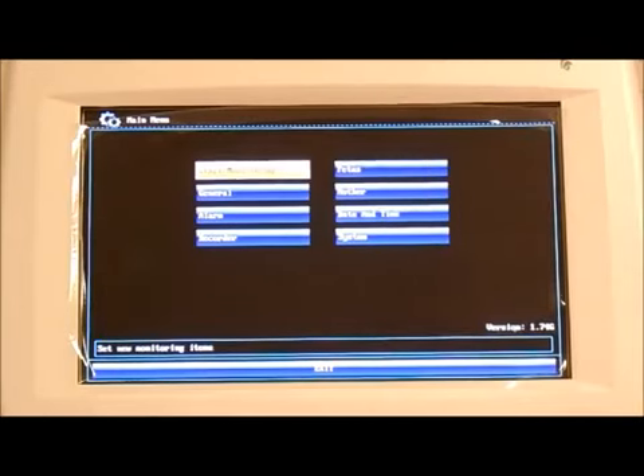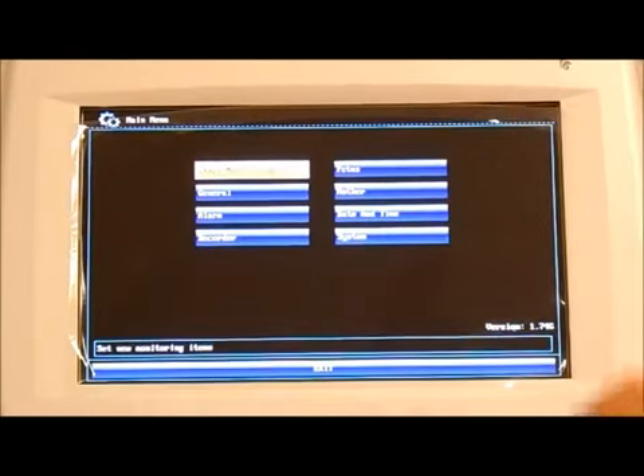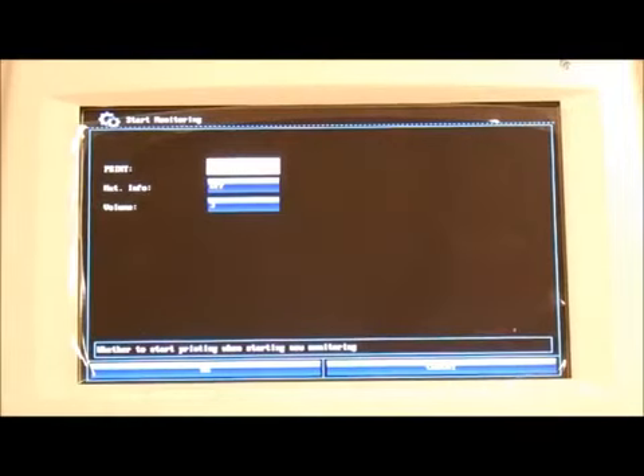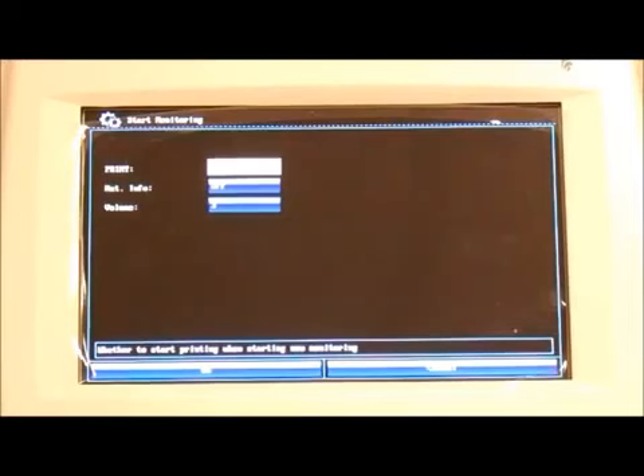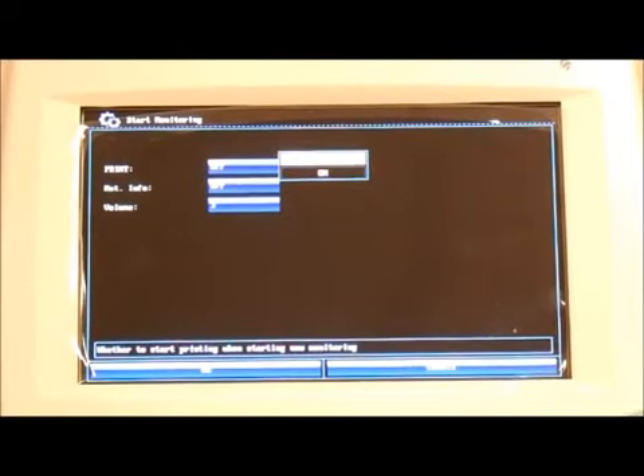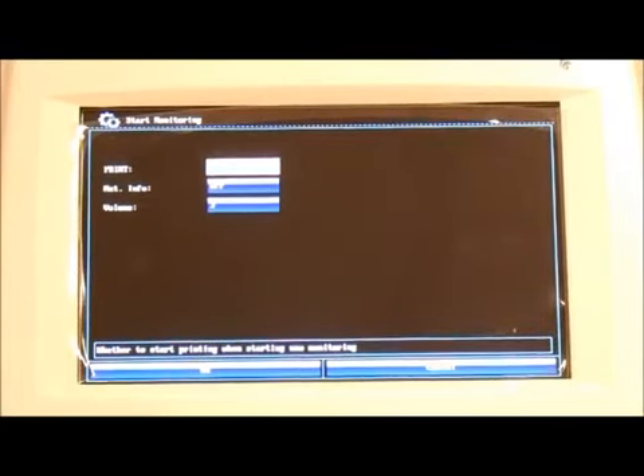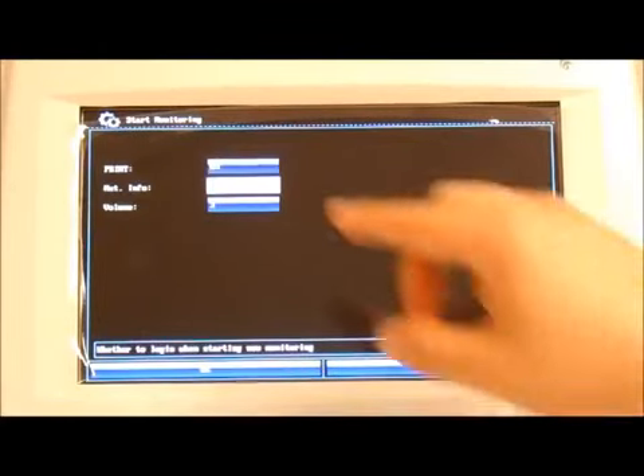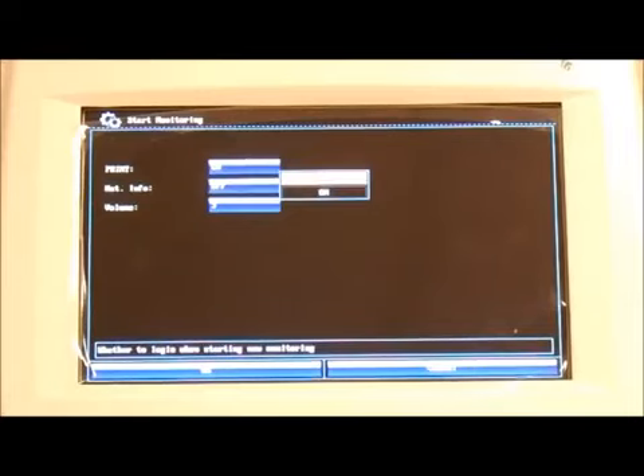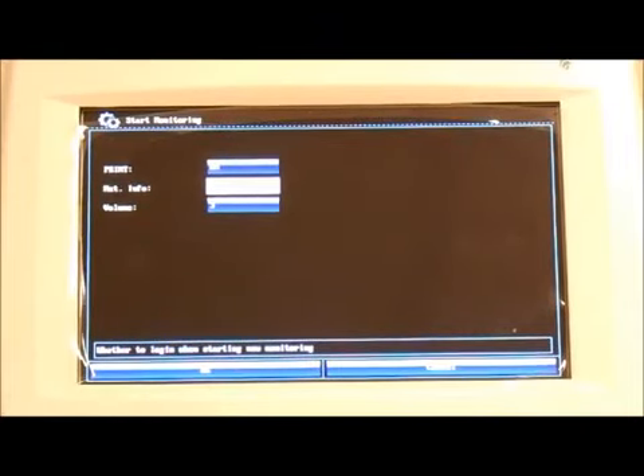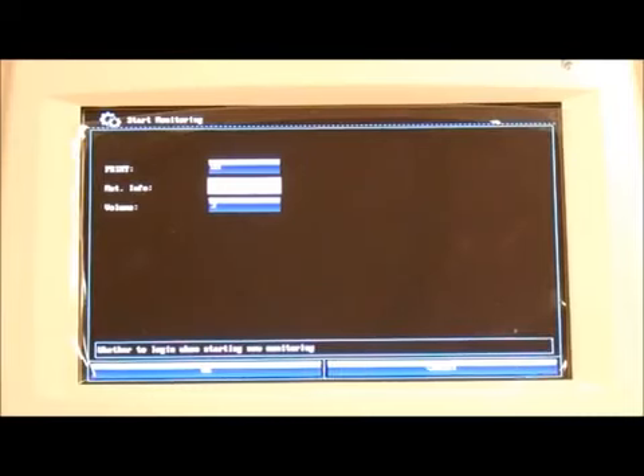The first tab is Start Monitoring. Through this menu, we can adjust what happens when we press the Start key. The first setting is Print. If it's set to off, the machine is going to start a new patient, but it's not going to start printing automatically. If we set it to on, after we press Start, you start a new session and the system automatically starts printing. Maternal info: if it's set to off, after pressing Start, the system is not going to ask you to enter the patient name. If it's set to on, it is.